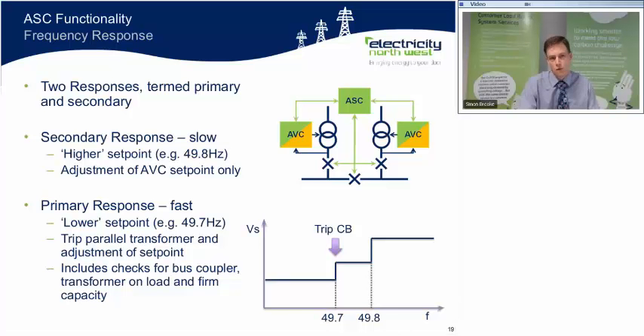So there is also a primary response, which is a fast response. So this would typically have a lower set point, for instance 49.7 Hz. And when the frequency falls to this point, the first thing we do is we trip one of the parallel pair of transformers. Tripping one of the parallel transformers effectively doubles the load in the other transformer, which doubles the voltage drop and hence has an instant effect on the voltage of the busbar. We follow this up by reducing the set point on the AVC relay because we don't want the AVC relay to correct this voltage reduction.